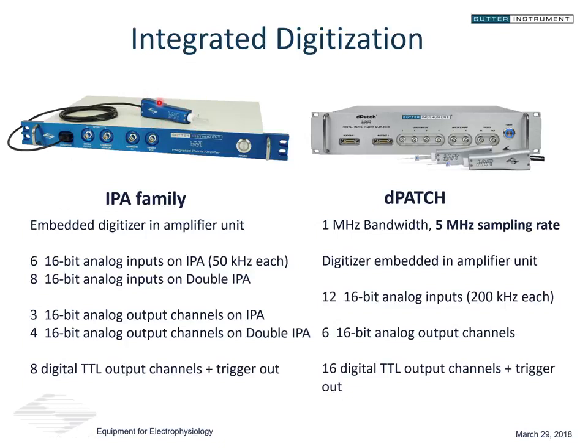In fact, for the D-patch, the preamplifier section, the analog section that's mounted to the head stage, is a separate box, a separate entity, and in that entity it has the calibration constants and its own independent A to D and D to A converter for that particular head stage. So those can be easily swapped around. If something is damaged there, there's no need for calibration because everything is stored in an internal EEPROM. So those can be easily changed, swapped out.